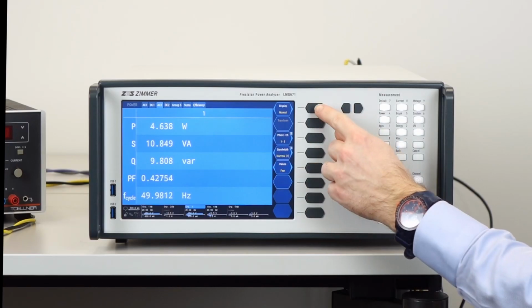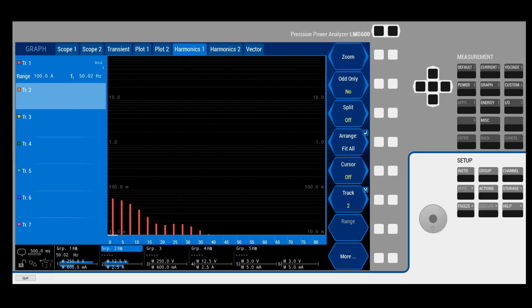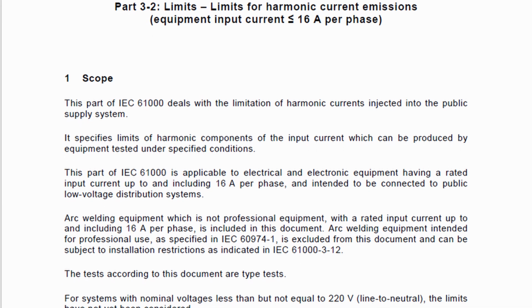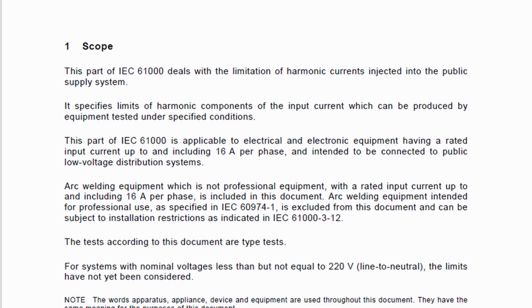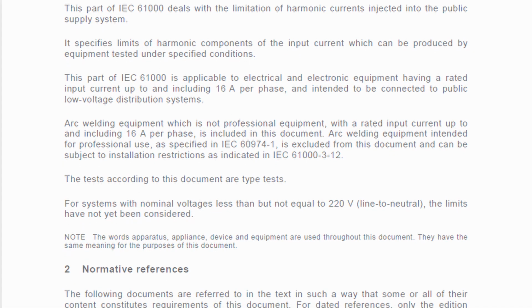Here, a Fourier transformation will give us a better picture of the harmonic pollution that the charger introduces to the grid. We immediately notice the absence of even harmonics and the wider spectrum. The total harmonic distortion of the current is almost 3 times higher compared to the linear power supply. To ensure good electromagnetic compatibility, this influence on the grid current must be controlled. There is an entire family of IEC standards that dictate methods of measuring harmonics and the limits of current harmonic emissions that different categories of devices shall comply with.